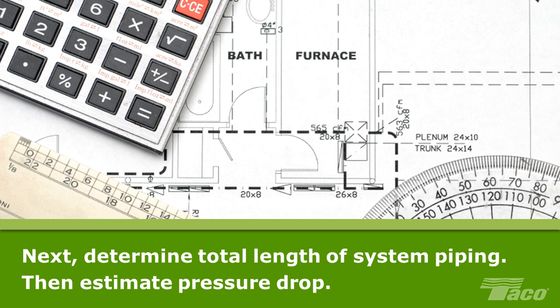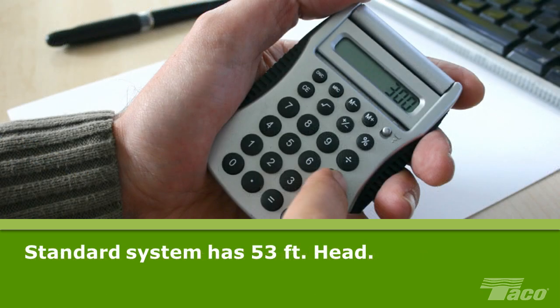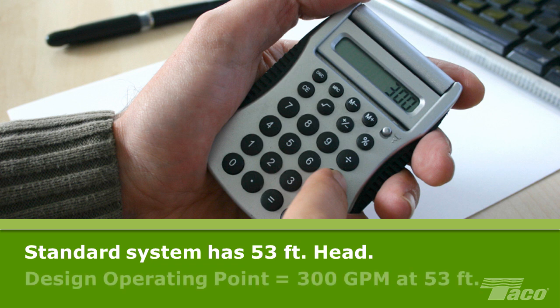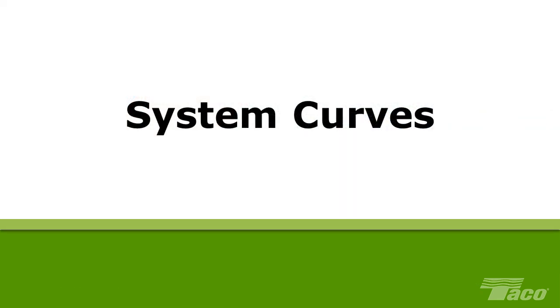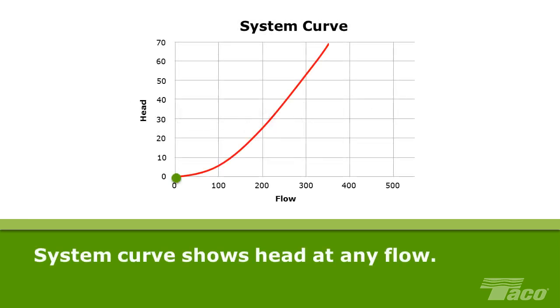The HVAC engineer then lays out the system against the building's architectural plan to determine the total length of the system piping. From that measurement, he or she can estimate the pressure drop of the piping, components, and fittings. Standard HVAC calculations indicate that this system has 53 feet of head. The flow requirements and system head establish the system design operating point, 300 GPM at 53 feet of head. System curves. A system curve graphically illustrates the system head at any given rate of flow. In other words, a system curve shows the combination of flow and head throughout the operating range of the system.